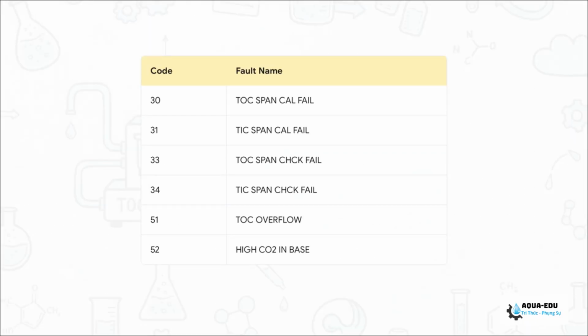Right before we actually calibrate, you need to check the analyzer's LCD touchscreen. Hop into the Maintenance and System Configuration menus and verify there are 0 active faults. Keep an eye out for things like code 30 for a TOC span cal fail or code 51 for TOC overflow. While you're at it, make sure the sample tubing is leak-free, there are no air bubbles, your flow rate is stable, and the waste line is completely clear.